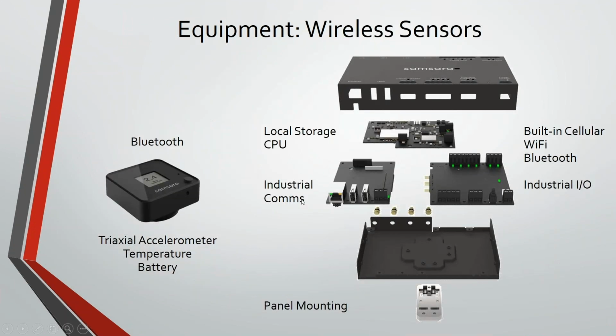And then that brings us to wireless setup. So what is a wireless solution typically going to consist of? Usually you've got your sensor, and that's going to be mounted on a machine. The sensor is in most cases going to have a triaxial accelerometer. Some of them have temperature, and almost all of them are going to be battery powered. Bluetooth is the most common way to communicate back to the gateway over here. So this over here is our gateway, and our sensor is mounted on the machine communicating Bluetooth back to the gateway.